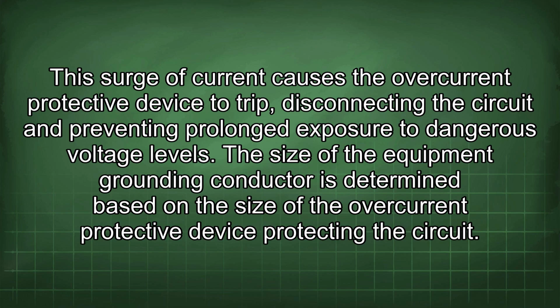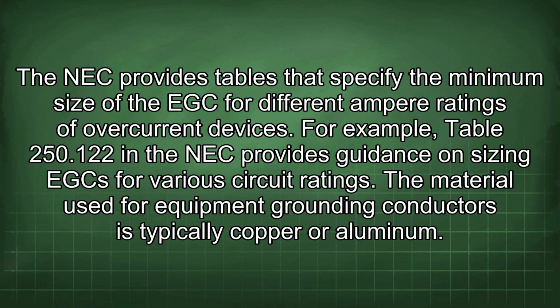The size of the equipment grounding conductor is determined based on the size of the overcurrent protective device protecting the circuit. The NEC provides tables that specify the minimum size of the EGC for different ampere ratings of overcurrent devices. For example, Table 250.122 in the NEC provides guidance on sizing EGC for various circuit ratings.